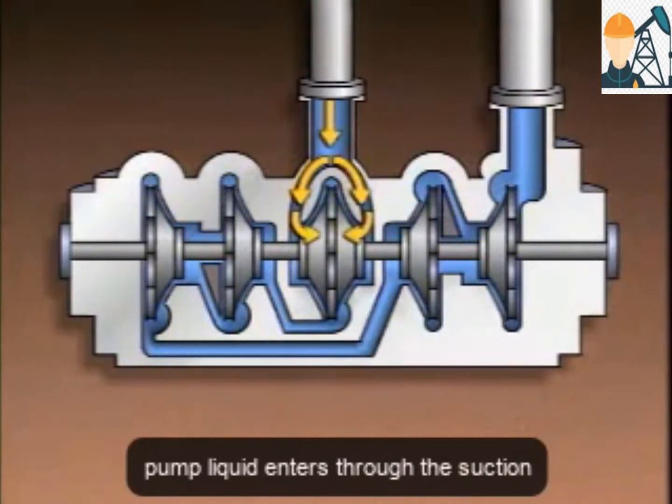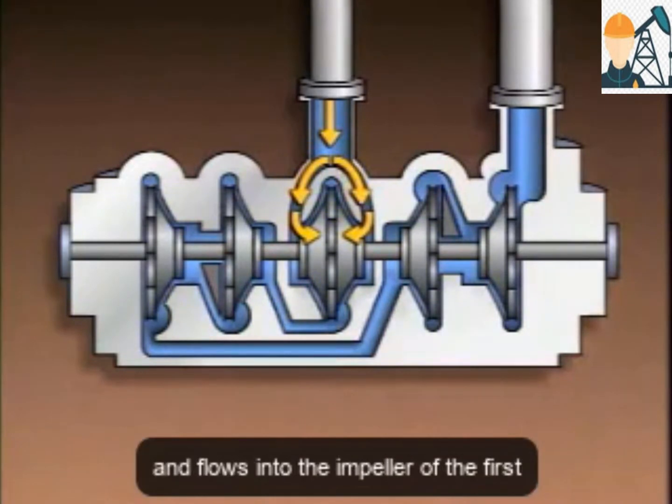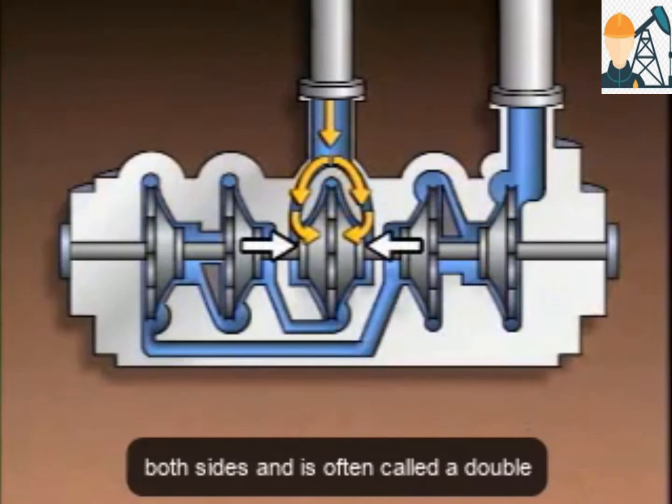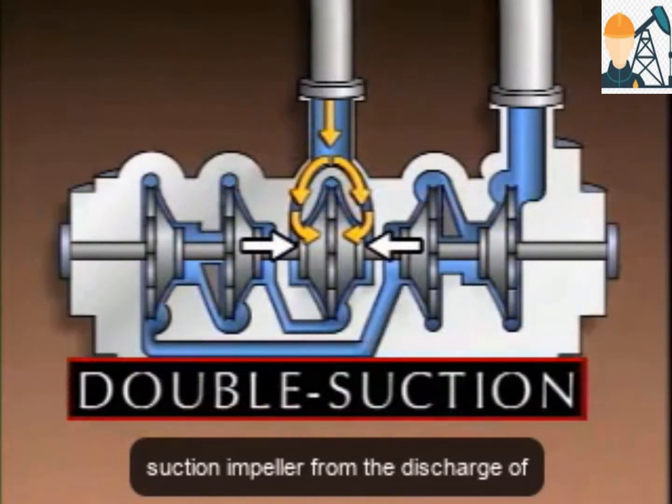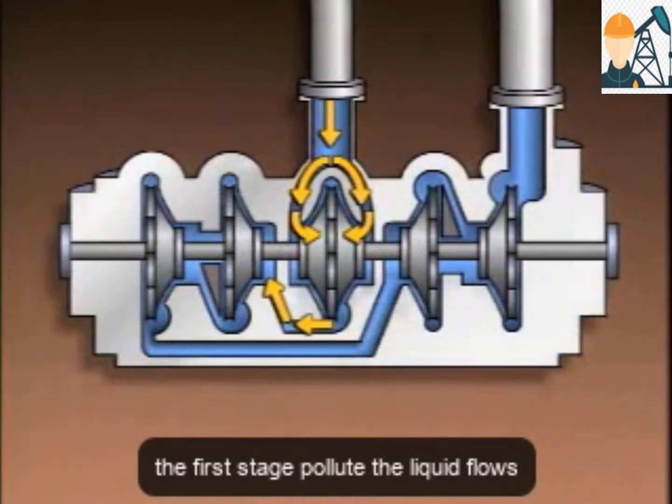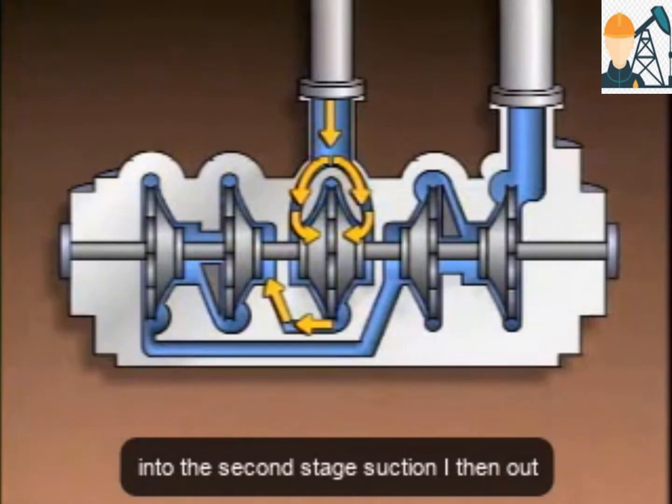In this pump, liquid enters through the suction and flows into the impeller of the first stage. This impeller has a suction eye on both sides and is often called a double suction impeller. From the discharge of the first stage volute, the liquid flows into the second stage suction eye.